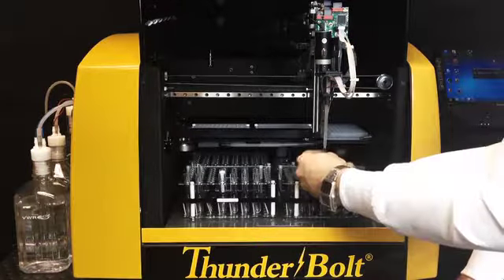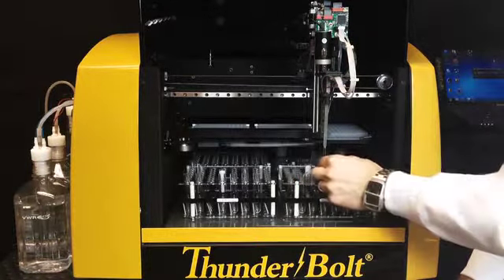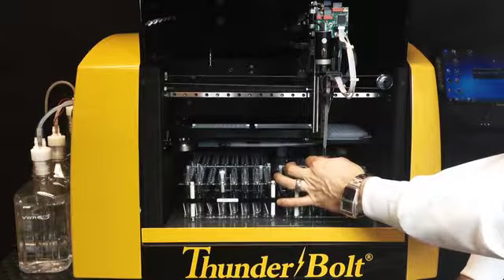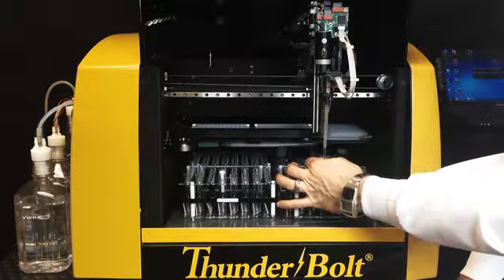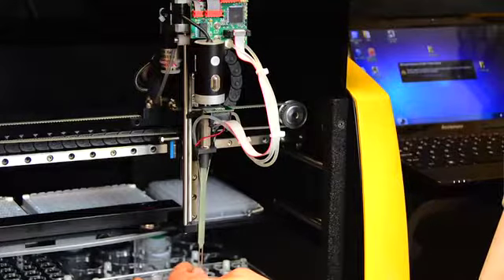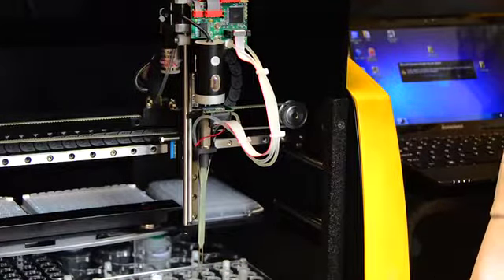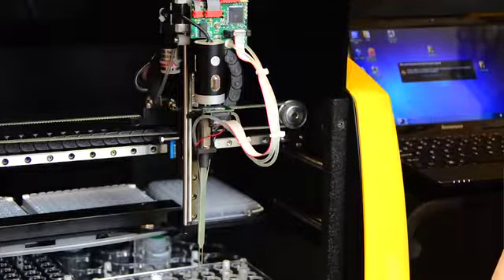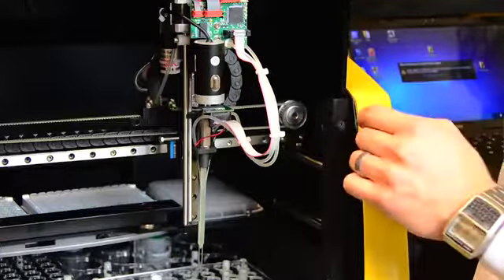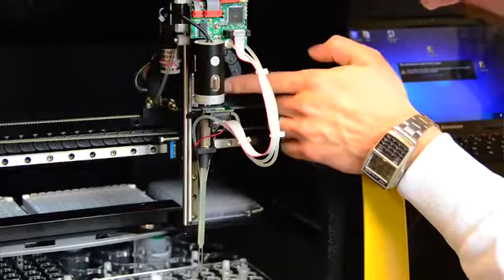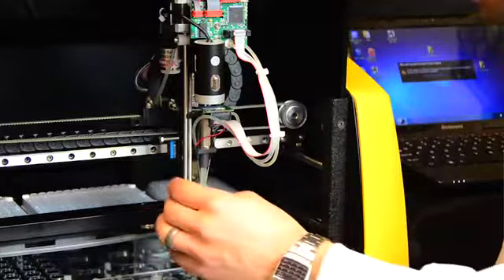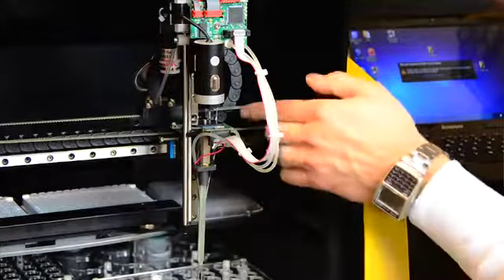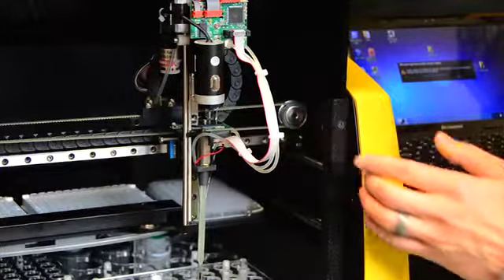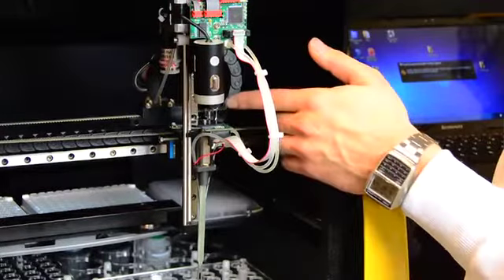And this, once again, is how it senses fluid. It's these two needles. Once it goes down and touches fluid, the conductance meter is triggered, and it tells the system, I am in fluid. Now, the reason we can pick up 1 microliter is because of this microsyringe back here. I mentioned this earlier, however, if you get more questions about it and you need to show them specifically, it's right here.